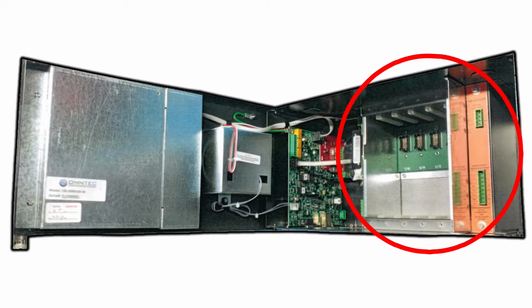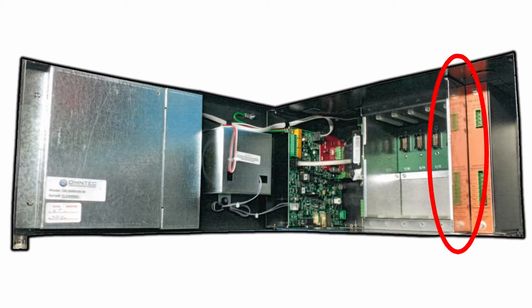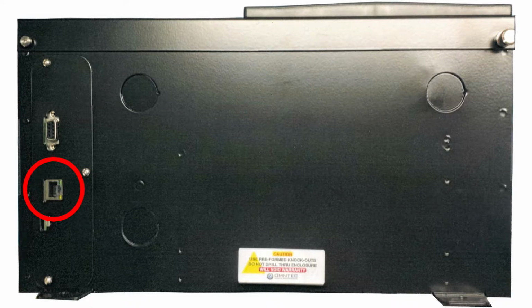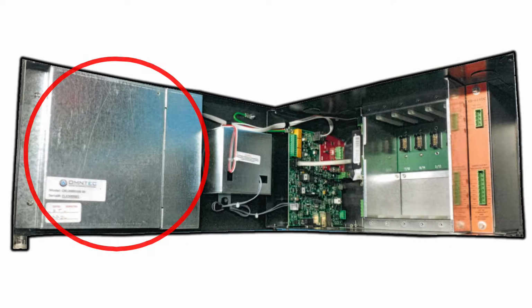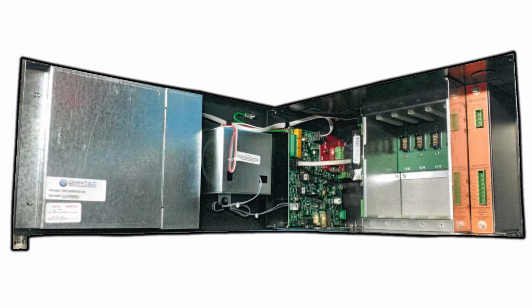On the back of the controller is mounted a backplane which will house the various interface boards, which are explained later in this presentation. The card cage will contain a metal barrier to separate the intrinsic and non-intrinsic boards. A total of 6 interface boards can be installed in the card cage, with a maximum of 4 boards of any one type. On the left side of the card cage is the unit's power supply. The TCP/IP, RJ45, and serial RS232, DB9 communication ports are located on the bottom of the controller. When the door is closed, the metal plate of the display and the metal barrier in the card cage produces an intrinsically safe compartment for the probe and sensor inputs.